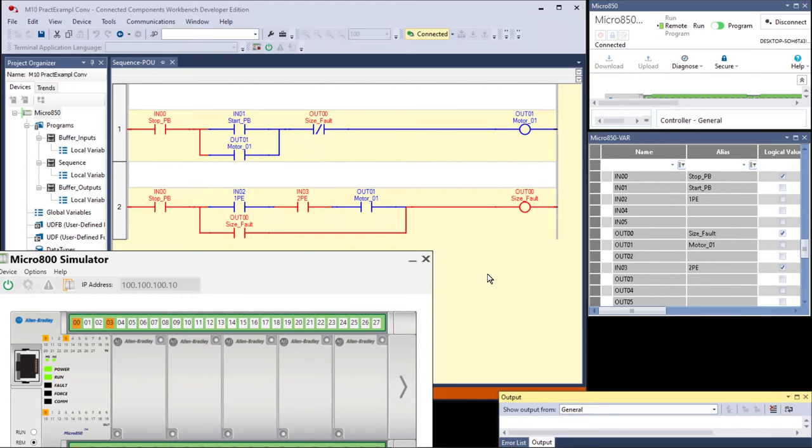So even with a little coast, if you're using VFDs, they have coast. With a variable frequency drive, you get some other options that you could use to stop quicker if you wanted to, with decel. But let's stay away from that. So there you go. That's how it works. If the operator pulled out the carton, then this would all be false. And so if you reset it, double click on zero. See, we lost the size fault. Let's start it back up.